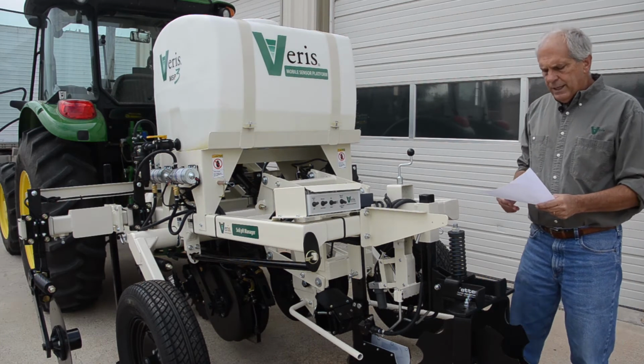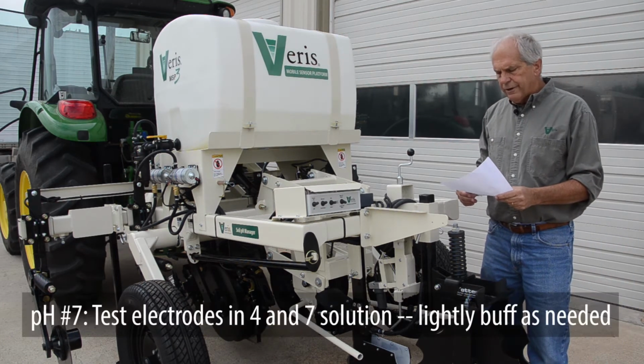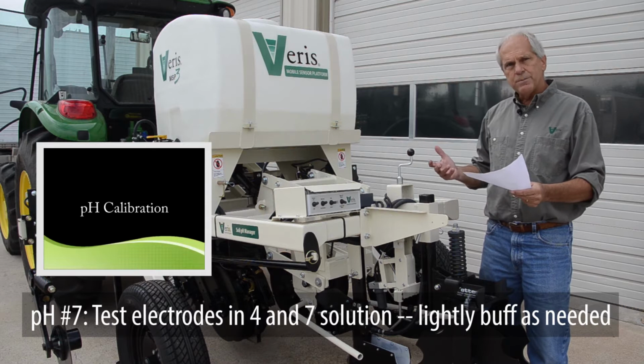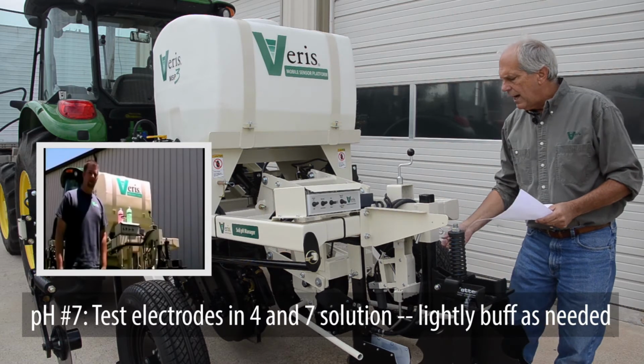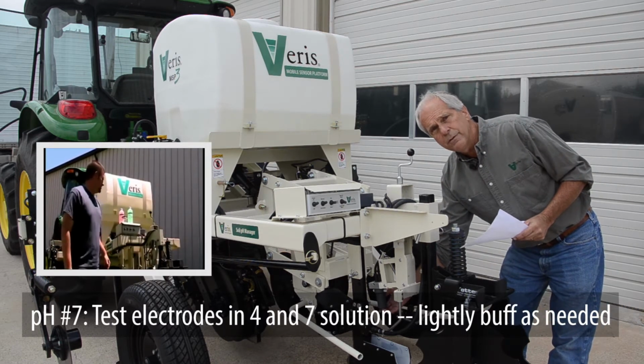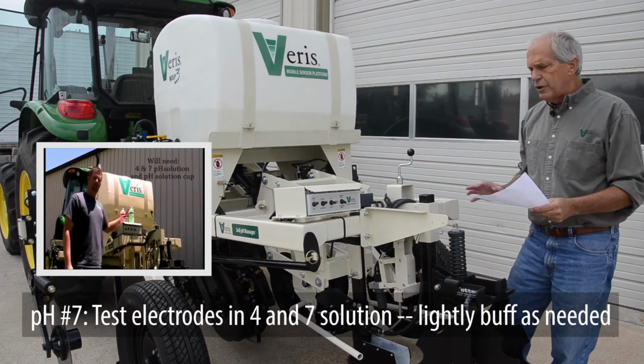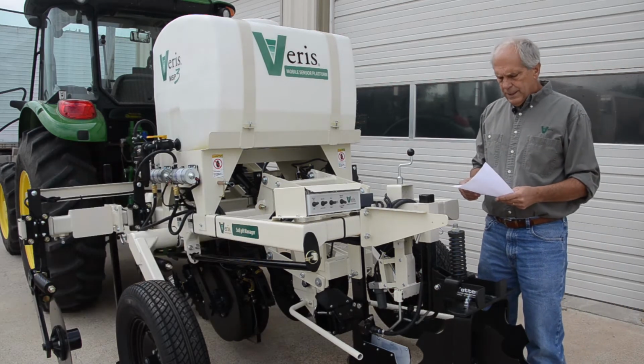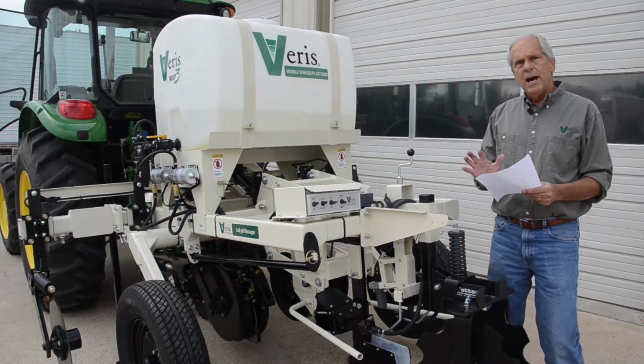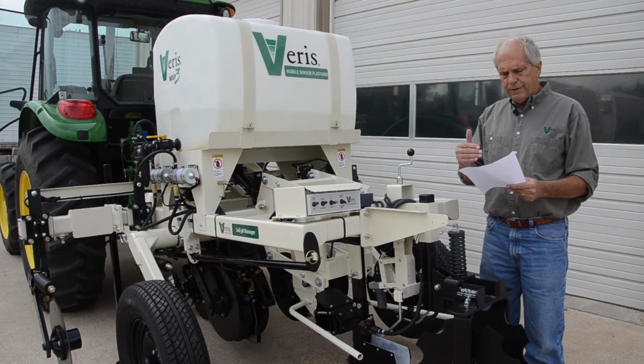The final item is to test the electrodes in a 4 and 7 solution, as part of the calibration procedure. These may need to be buffed lightly with sandpaper if you don't get a good calibration. So those are the 7 items that are part of the pH pre-flight checklist.